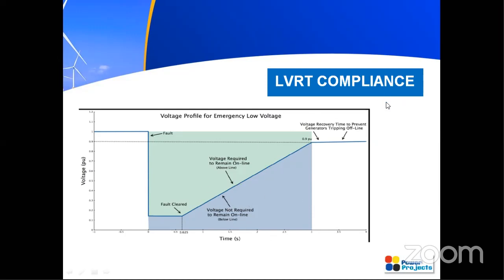So this is the LVRT compliance. When you have a wind farm, you have to do LVRT studies. You have to see the dynamic performance and then you have to get the LVRT compliance. This is highly essential. And during this voltage dip, the reactive power supply is of first priority and the real power supply is of second priority. So the first priority has to be given to the supply of reactive power.